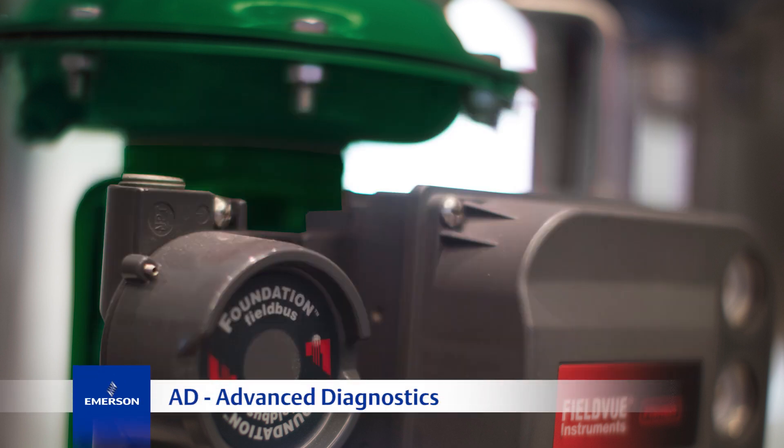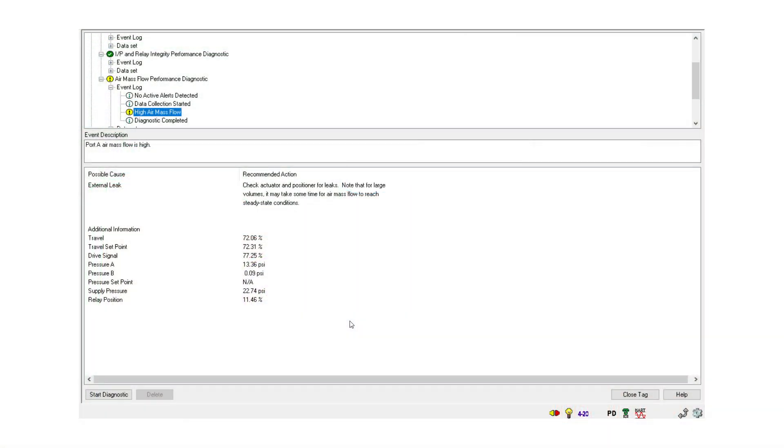AD Advanced Diagnostics and PD Performance Diagnostics are the same in Fieldbus as they are in Hart, with one exception. The PD one-button diagnostic in Fieldbus does not require the user to initiate the test because it runs continuously, whereas with Hart, the user must initiate it.